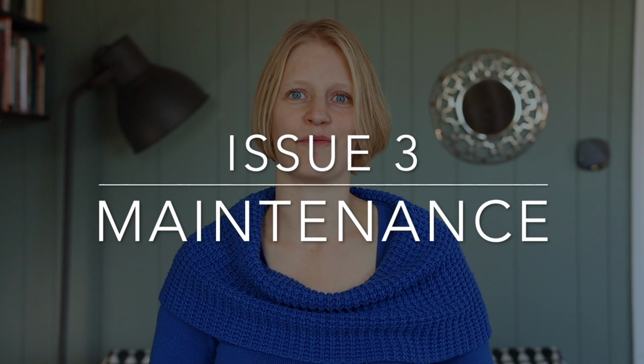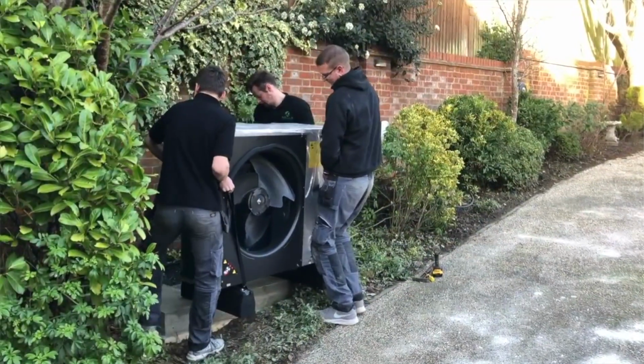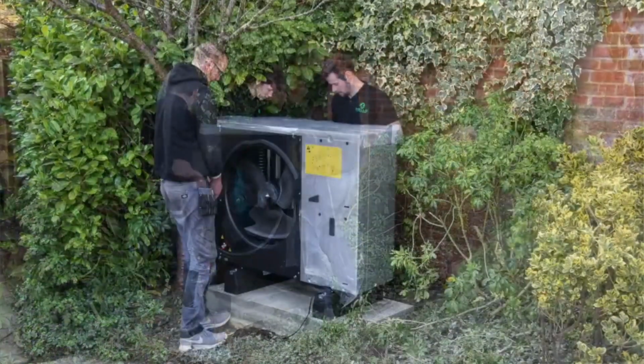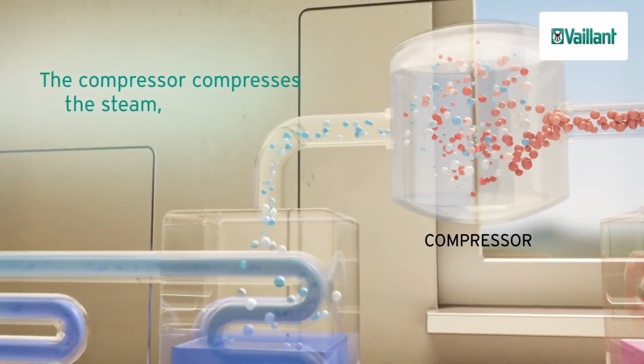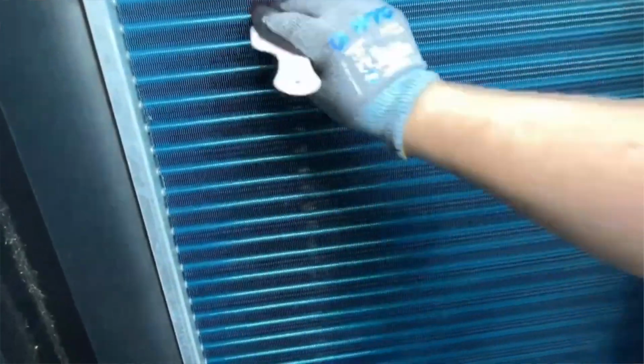temperature throughout the home. Oversized heat pumps also come with financial costs. Besides the high upfront cost, an oversized unit will need to be replaced sooner than a properly sized unit. The higher kicking on and off frequency of running below the optimal capacity can lead to more rapid deterioration of the compressor and other parts, so more wear and tear. This, in turn, may result in more frequent repair and a shorter overall lifespan for your heat pump.